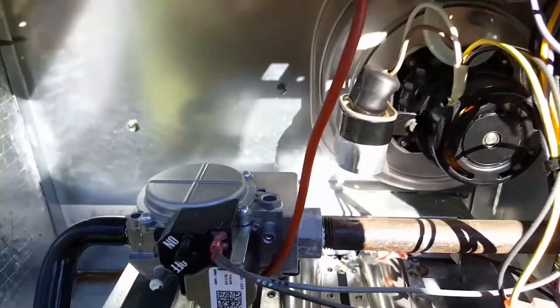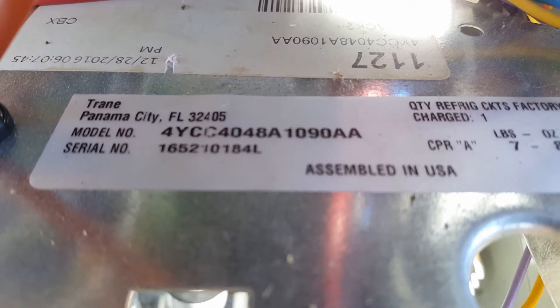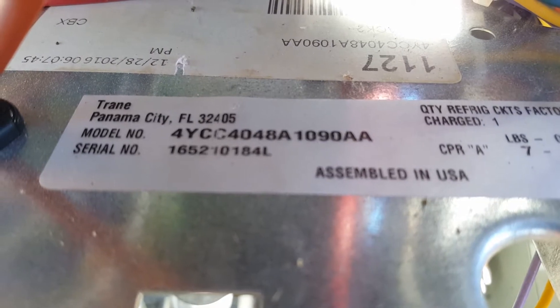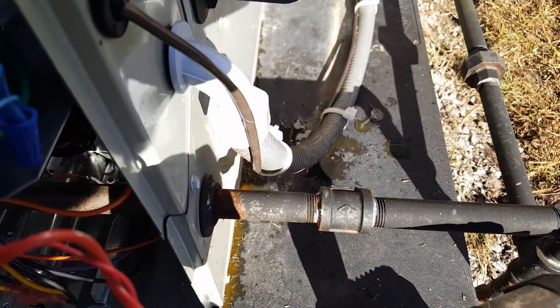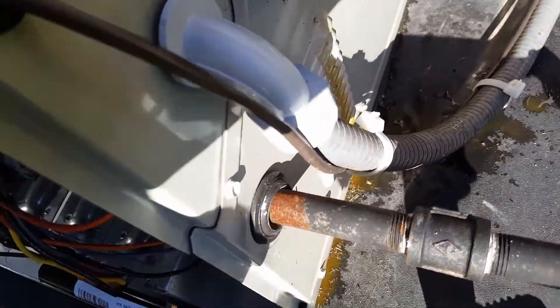Here's my request that Trane make something right out of this, because I have dozens of customers with these units that all have the same problem. Now if you hear the combustion blower, it actually sounds pretty horrible. Spitting a lot of rusty water out of there. See all that rusty water on the side of the unit?